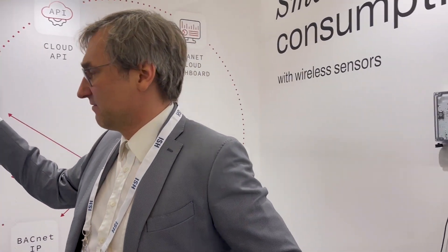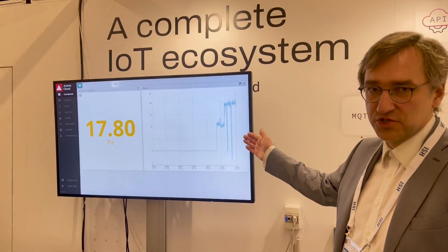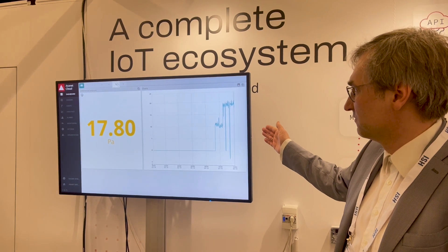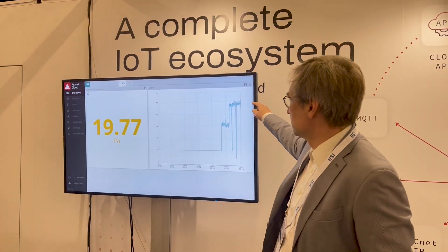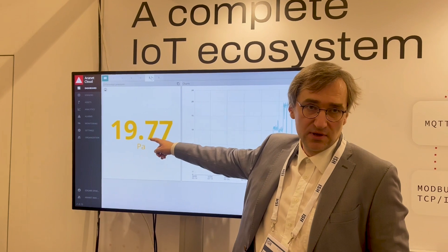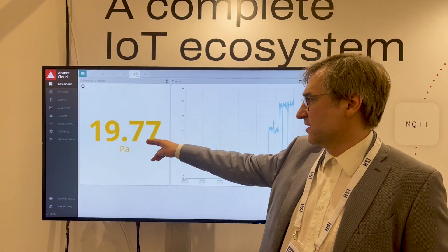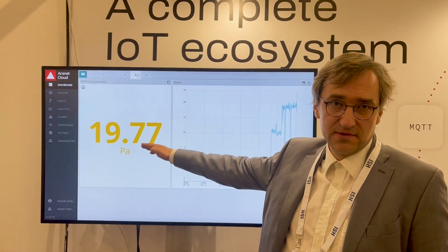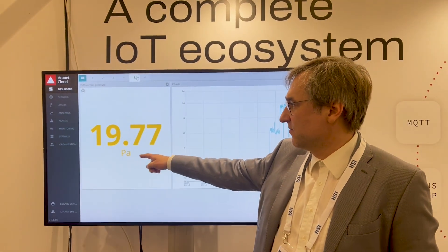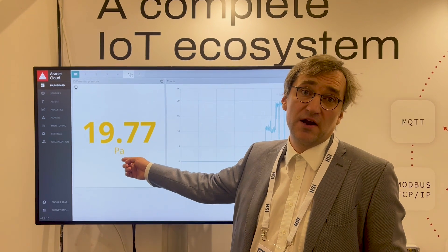And here I have a computer connected to our cloud, and I can see the current readings. I see that it's approximately 20 Pascals, and the value is yellow, because I put an alarm that should warn me if it's above 18 Pascals.